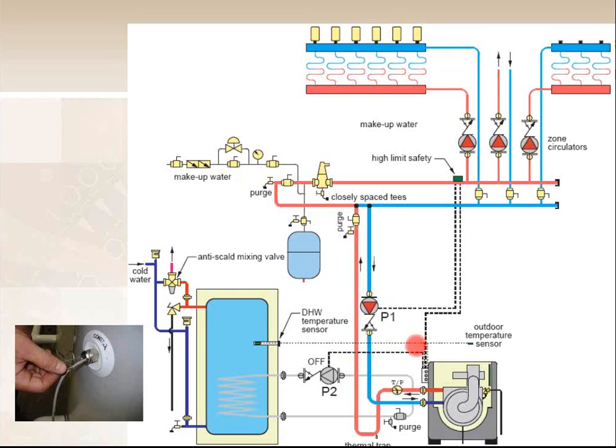Pump number 1 is controlled by the boiler. He decides when pump 1 shuts on and off. And he provides water through this primary loop. Everybody else grabs water as they need it. So for example, if pump 1 is moving 10 gallons of water, great. And let's say for sake of argument, these other 3 pumps are 4 gallons each, so 12 gallons total. If pump 1's on and this first radiant zone turns on, great. 4 gallons go up to that top loop. And then the other 6 gallons of P1 just circulate back through, right, across this crossover bridge here.